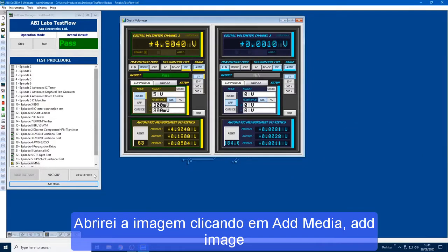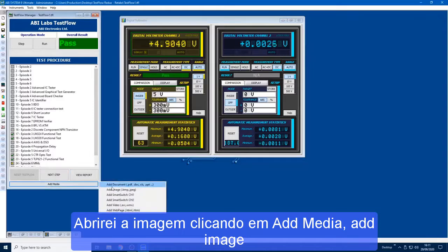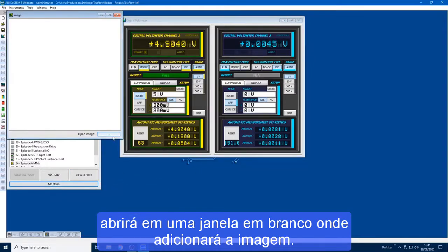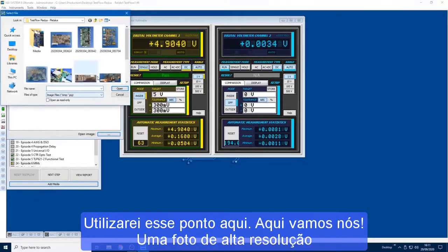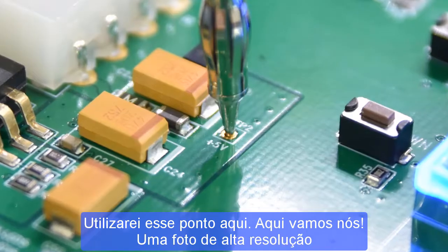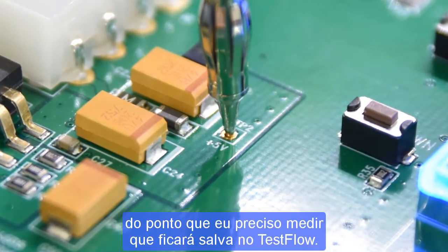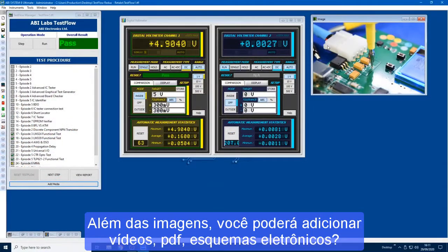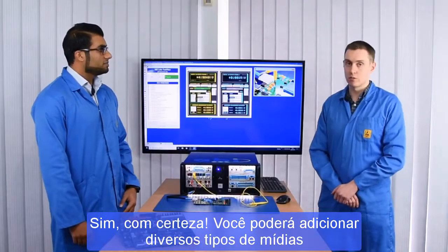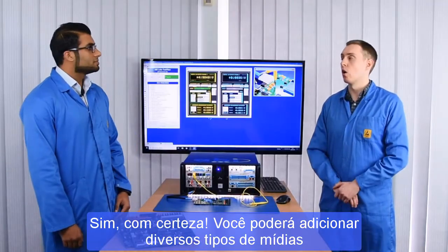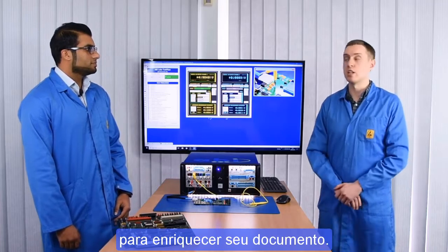I'll open that up here under Add Media, Add Image, which opens up a blank window for you to add your image, and I'll use this point here. There you go, a nice high-res photo of the point that I just measured, and that'll be saved in the test flow. So it's not only images, you can also add videos, PDFs, schematics and things like that? Yes, of course, so you can add a wide range of media to make it a really rich document.